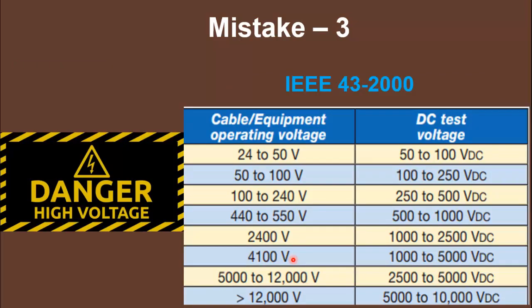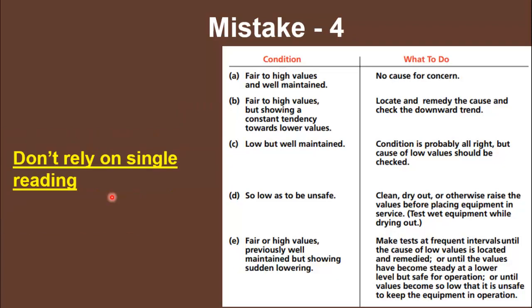The third mistake is applying the wrong test voltage. According to IEEE standard 43-2000, there is a list of test voltages to apply based on the equipment's rated operating voltage. For example, for equipment rated between 400 to 500 volts, the test voltage should be between 500 to 1000 volts. Please follow this chart to apply the correct test voltage, otherwise there is a danger of damaging the insulation of that equipment.